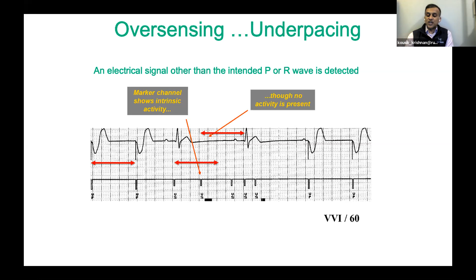So oversensing means that it senses something that it's not supposed to be sensing, which leads to underpacing, which leads to a heart rate slower than the lower rate limit. And you may not know what it's oversensing by looking at the surface ECG. Sometimes you can tell, but you will often have to do an interrogation. And even then you can sometimes not really know what it's oversensing. You just know that it's oversensing something, which leads to underpacing.